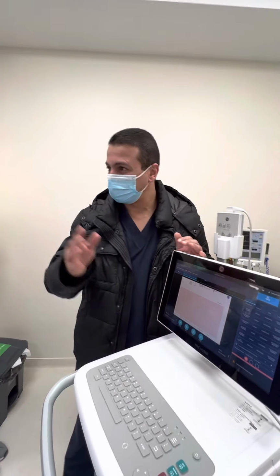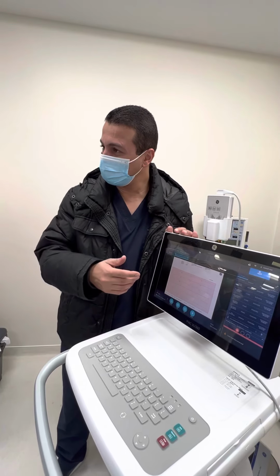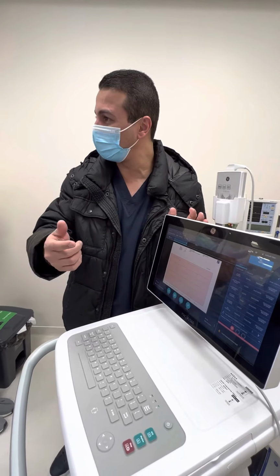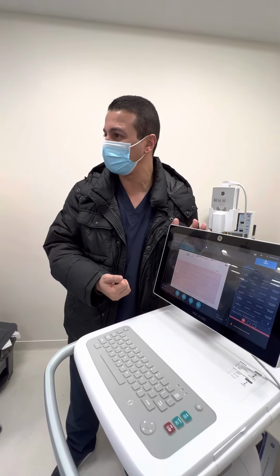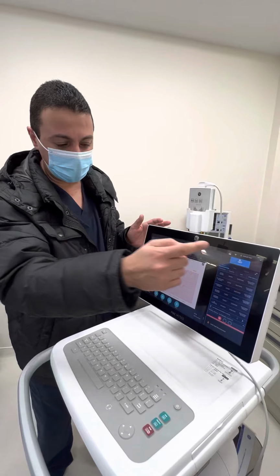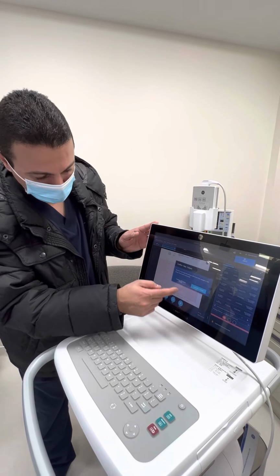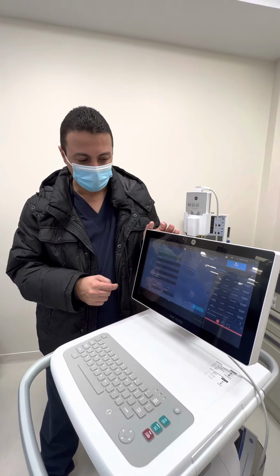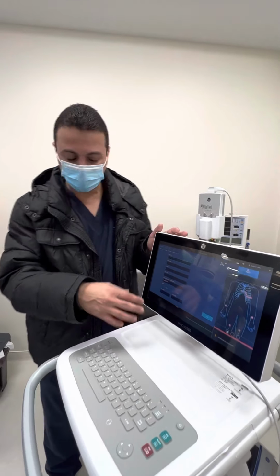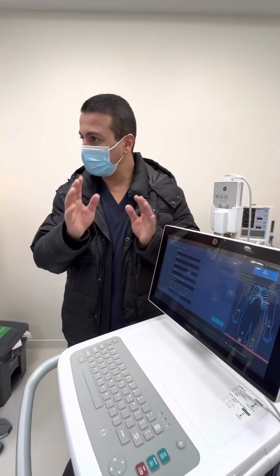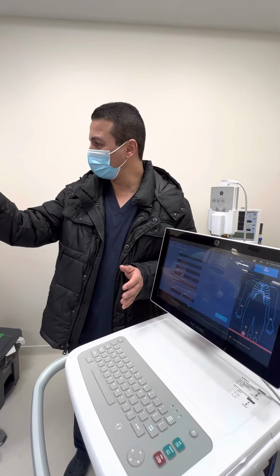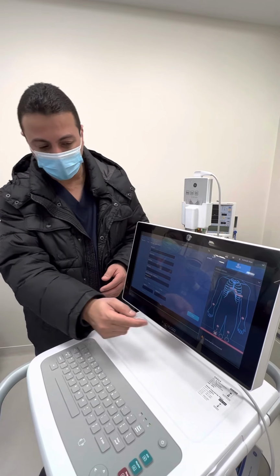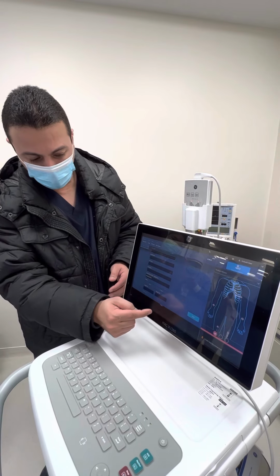We have the order list. Let's use it. We have a better way actually to retrieve the patient demographics with the order if we place the order before we run an ECG for our patient. New patient, use one of the MRNs. So it was asking if it is the new patient or the same patient.